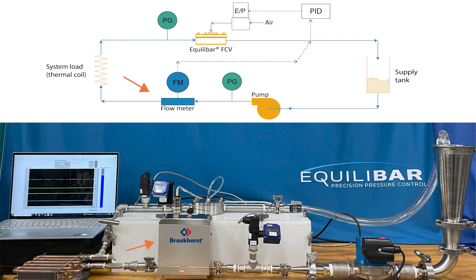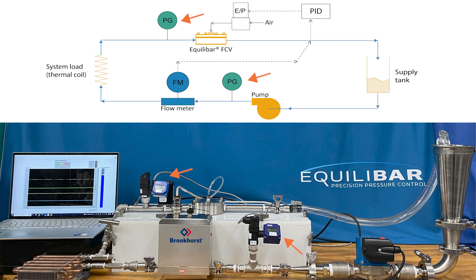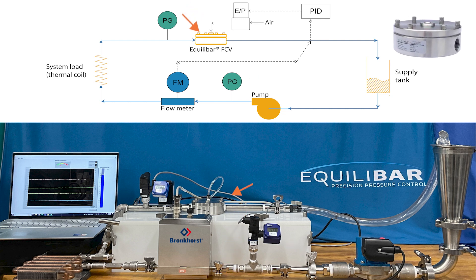We have installed a Bronkhorst Coriolis mass flow meter to provide precise documentation of our valve authority. We have a heat exchanger coil as our resistive load; DP increases exponentially with flow across the coil. The coil is an analog for any fluid resistance such as a filter membrane, an orifice, or a long run of pipe. We have pressure sensors after the pump and before the control valve so that we can calculate the valve authority accurately using delta P. We are using an Equilibar half-inch GSD4 control valve to control the flow. Our ability to control at low valve authority allows us to install a larger valve here to get more thermal capacity out of the pump while also not losing control. We circulate the water back to the supply tank.